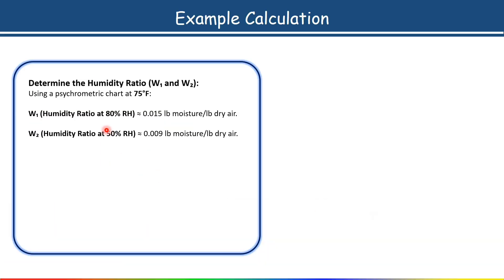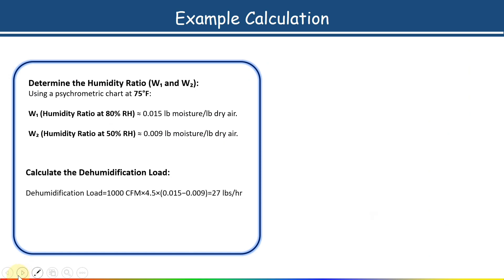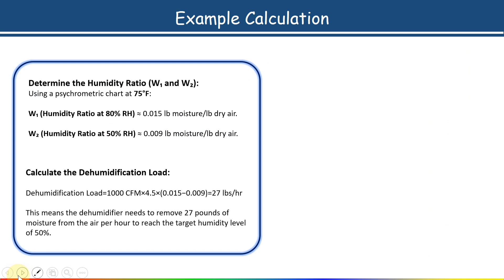Now substitute the values into the dehumidification load formula: Q = 1,000 CFM, conversion factor 4.5, W1 = 0.015, W2 = 0.009. The result is 27 pounds per hour. This means the dehumidifier needs to remove 27 pounds of moisture from the air per hour to reach the target humidity level of 50%. This is how we select and size the dehumidifier. Please like and subscribe to the channel for more informative content.